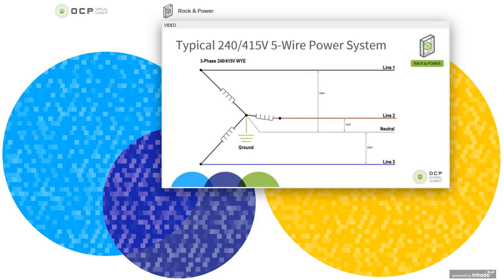One other note on these, there is a neutral in here, and you think, how can I have three lines and only one neutral? But because of the way three phase is distributed, and each phase is 120 degrees out of phase with the next phase, the neutral currents tend to cancel each other out. So even if there is some harmonic current, it does not exceed the current carrying capacity of that wire.